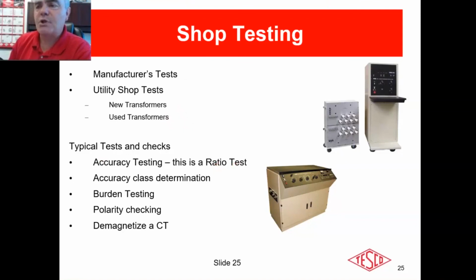The typical tests and checks that we would do in the shop are the ratio test, the accuracy class determination, the burden test, polarity check, and demag. In the, hold on one second here.